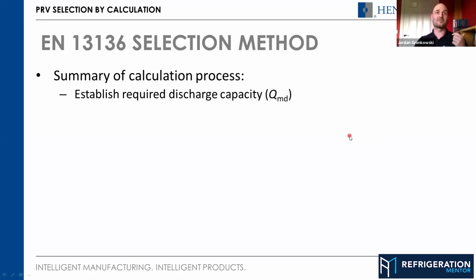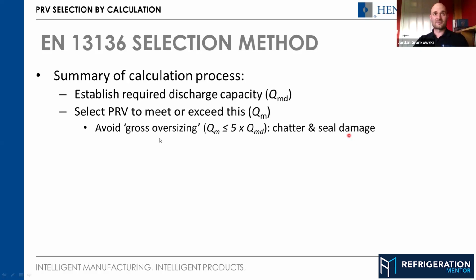So just to summarize, establish your QMD, then select the right PRV to meet or exceed that in your QM. And this is where I've mentioned gross oversizing, that we touched on earlier. There is no definition given in the standard about what gross oversizing is. It just says not to do it or to avoid it. Based on some research we've done and some independent research, we typically classify gross oversizing as 5 times. So if the valve has 5 times the flow of the required flow, then we would call that grossly oversized. And that's where the chatter and seal damage we talked about earlier can come in.